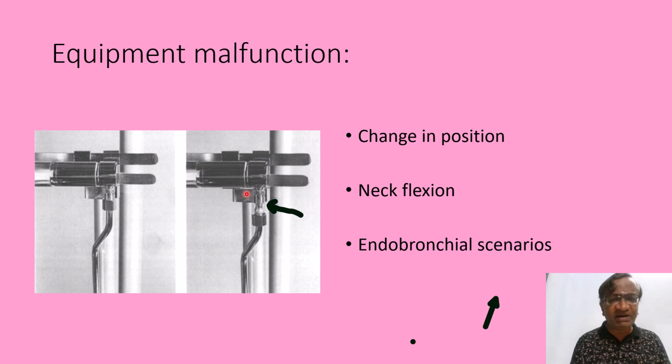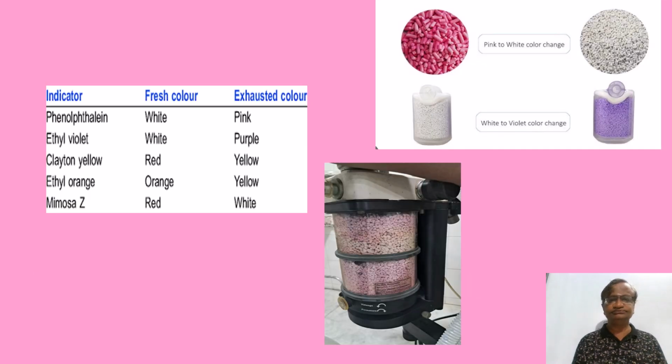Here there may be an equipment malfunction. Very common is soda lime exhaustion. It has come like this. Unless you change it, it is not going to be useful. Otherwise, you have to increase the flow to normal.